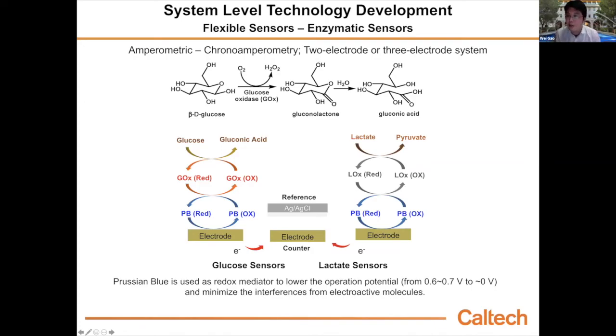Generation one works by detecting hydrogen peroxide. We are actually using a generation two glucose sensor, utilizing a redox mediator - here we are using Prussian blue. One major reason we use Prussian blue is that we can operate the glucose sensor at a very low voltage. If we want to detect hydrogen peroxide based on a generation one glucose sensor, we need to apply a very high voltage, like 0.6 or 0.7 volts. But with generation two, using Prussian blue as a redox mediator, we can operate the sensor at around 0 volts, which minimizes the influence from other electroactive molecules.